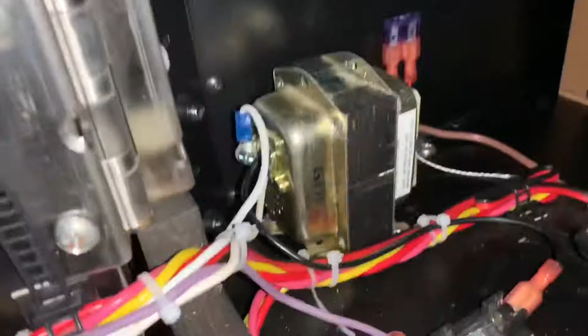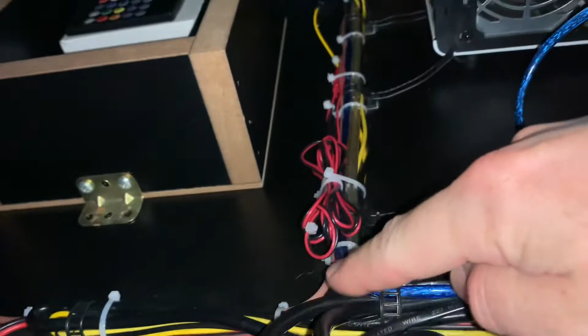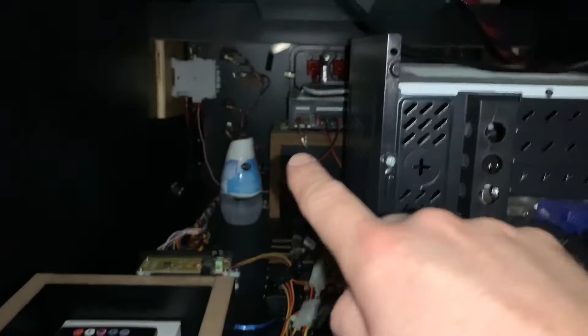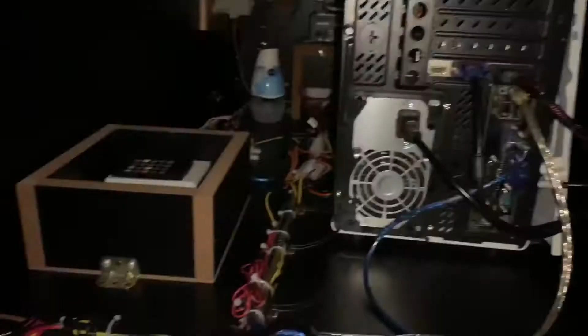So power comes from the switch, goes through a fuse block, and 120 volts powers the step-down 24-volt transformer. Off the 24-volt transformer, you can see we fused it, then ran some thermostat wire, which feeds straight to the front of the machine and splits, teeing off either way. You can see one contactor up there and one over there. Let's move to the front of the cabinet and I'll show you the contactors.